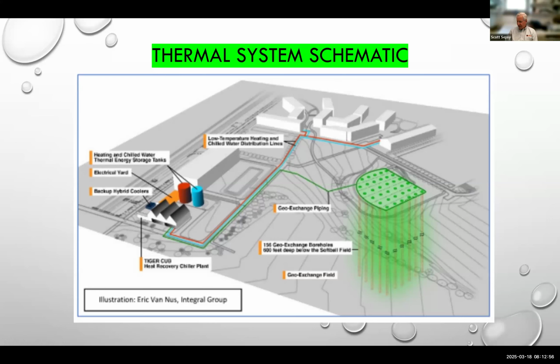We have about 1,000 geo-exchange wells now on the main campus and need to drill about 900 more as we build out the system. These wells are typically 600 to 800 feet deep. Some of the wells there have temperature sensors every 50 feet of depth to help monitor and operate the plant. We also have 3 small geo-exchange systems for clusters of graduate student housing and an arts complex.